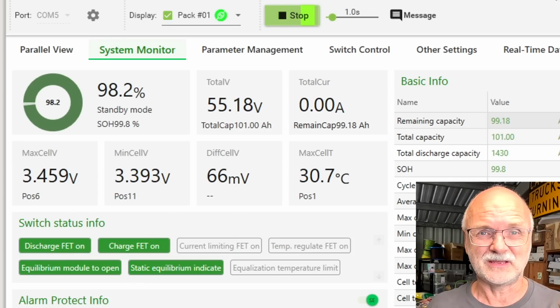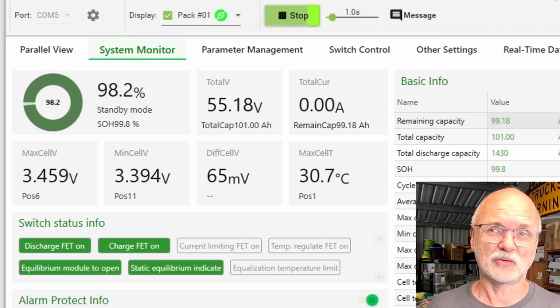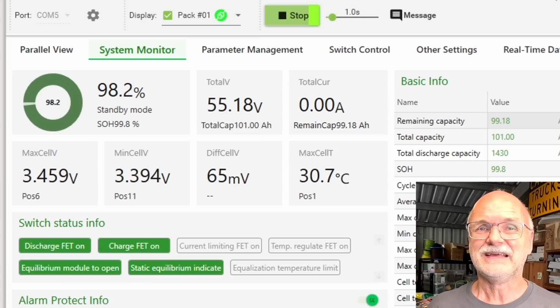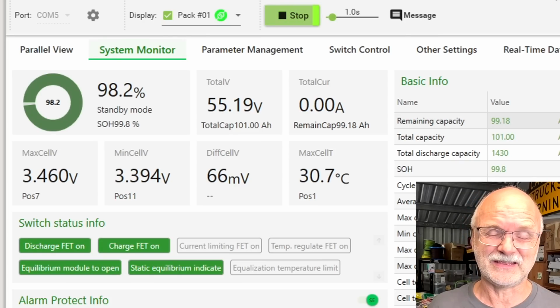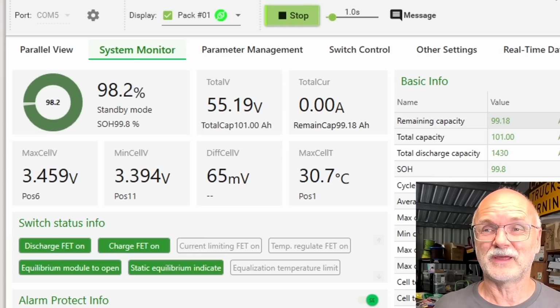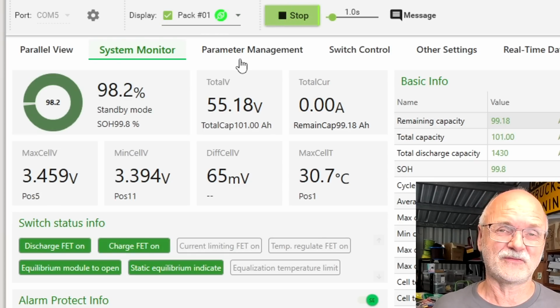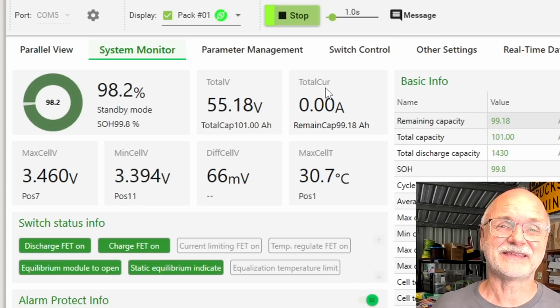I guess they tested this in a controlled laboratory environment. So if I connect the power supply to this battery now and keep it at 55.2 volts constantly at the standby mode here, I'm sure we will see a 100% reset after 15 minutes then. But this is not the reality. Once the BMS is installed in the battery and connected to solar and load, the voltage is not constant at 55.2 volts, and neither is the current at 0.